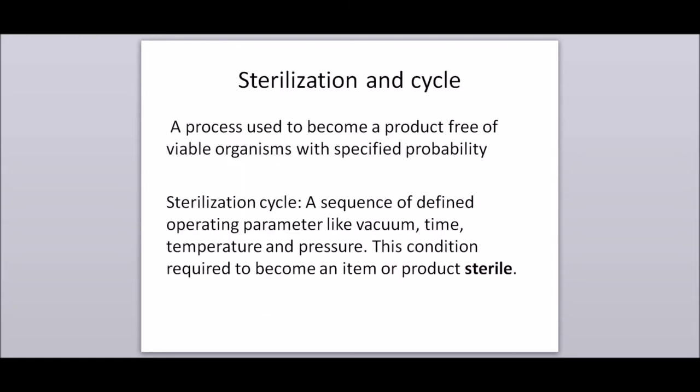Sterilization: a process used to render a product free of viable organisms with a specified probability. Sterilization cycle: a sequence of defined operating parameters — like vacuum, time, temperature, and pressure — required to render an item or a product sterile.